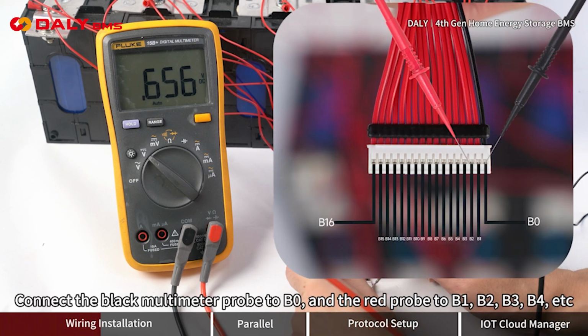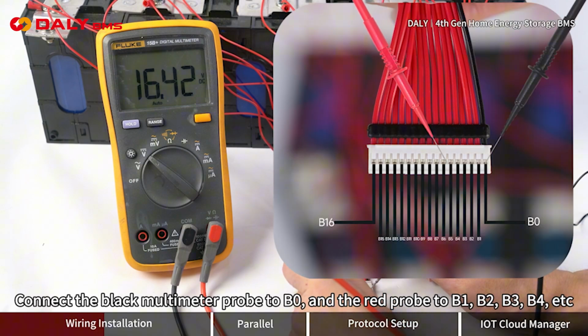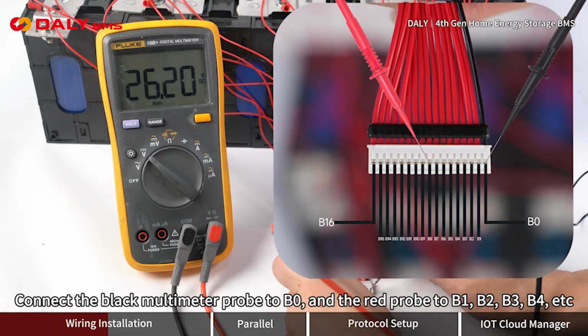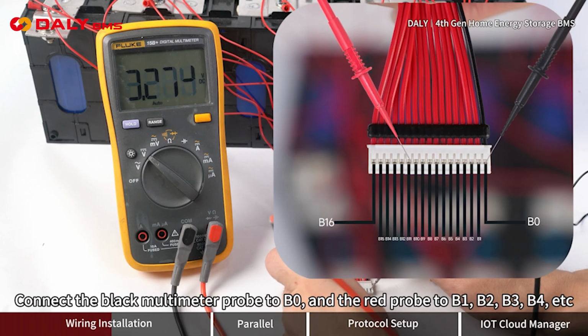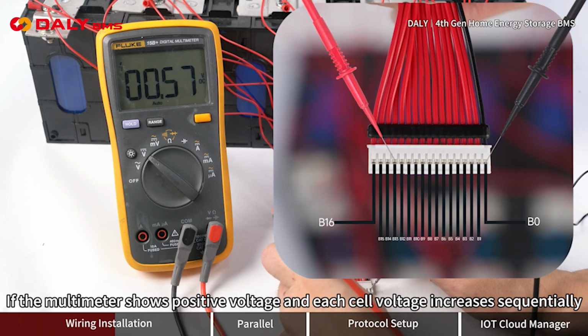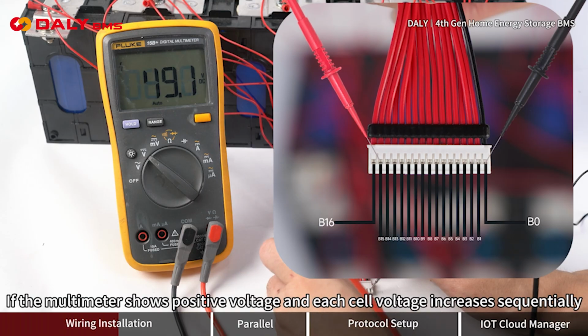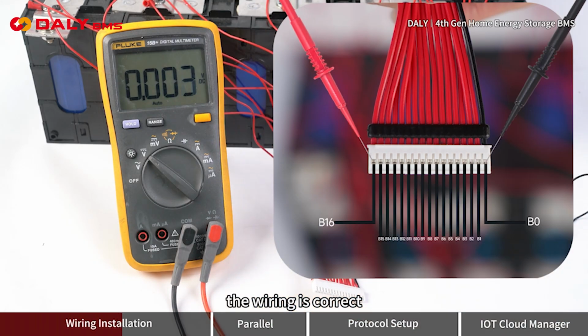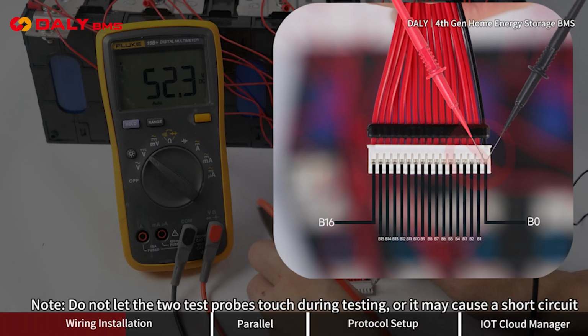Connect the black multimeter probe to B0, and the red probe to B1, B2, B3, B4, etc. If the multimeter shows positive voltage and each cell voltage increases sequentially, the wiring is correct. Note, do not let the two test probes touch during testing, or it may cause a short circuit.